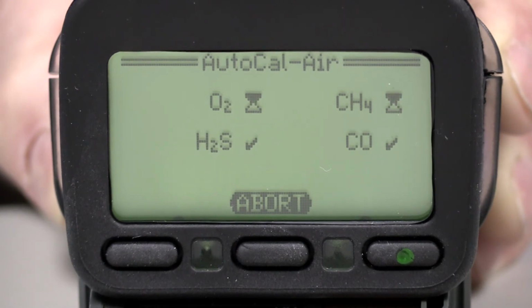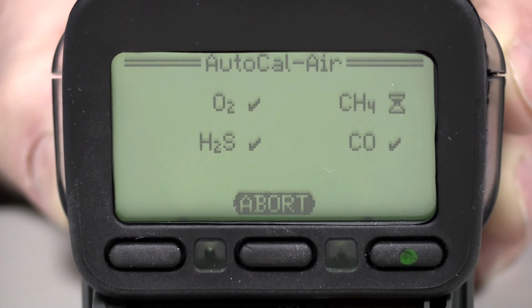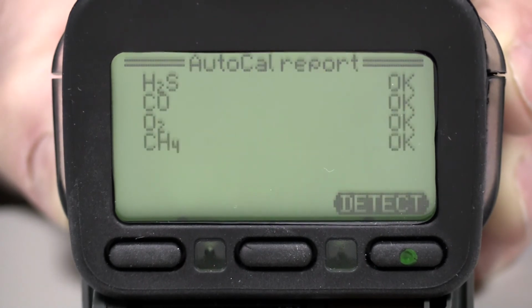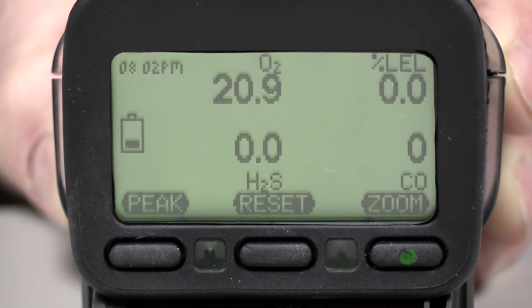The display will show an hourglass icon for the sensors while they are being adjusted, then a check mark when the adjustment is complete. The instrument will briefly display a screen showing the instrument has been successfully fresh air adjusted, then return to normal operation. The readings should now exactly match the expected fresh air concentrations. The next step in the calibration procedure is to adjust the sensors while they are exposed to calibration gas.